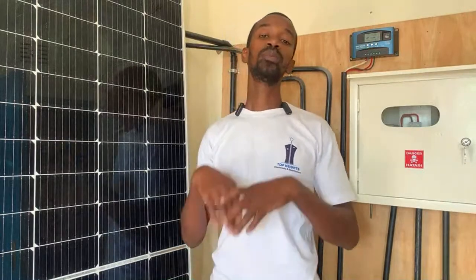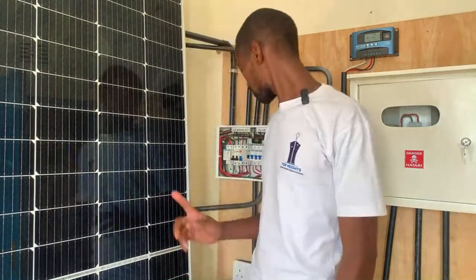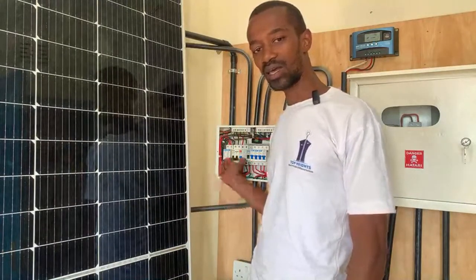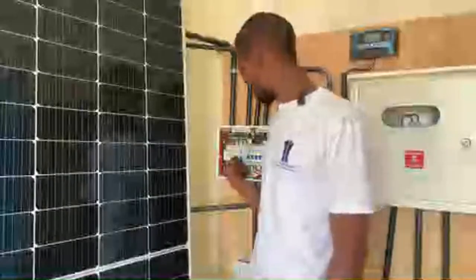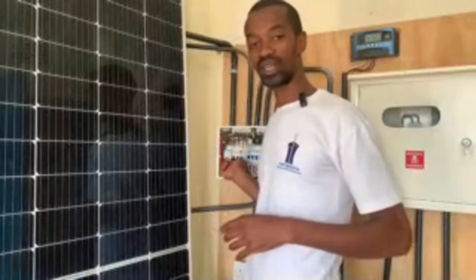Another aspect is if the main switch is of poor quality, it will be affected by the heating circuit. That heating circuit, where you have a kitchen appliance that is heating - probably an undersink heater used whenever utensils are being washed - will affect this MCB. This happens if the connection is loosely done, if the MCB is of poor quality, or if the size or rating of the MCB is too low or small.